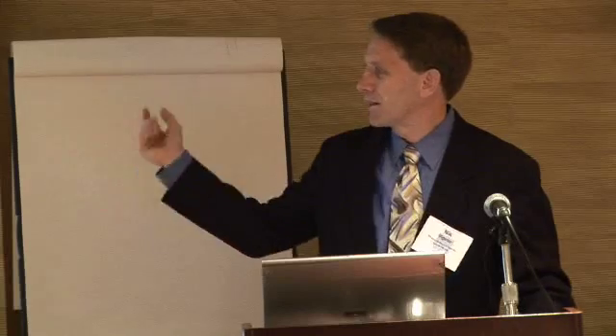And the best time to use it is if you have a lot of contrast between the warm building and the cold exterior. You can see I took this picture in February of this year, when it's tremendously cold, and you can see the hot air is flying out of the building. Good analysis tools, but I don't know if the gentleman who was in the church yesterday with the infrared camera, he was sort of holding it up in the church, and there was not enough contrast there to really read anything. And that's why when you look at buildings, you got to get up at 2 in the morning in January and carry your infrared camera out there. September just won't work.